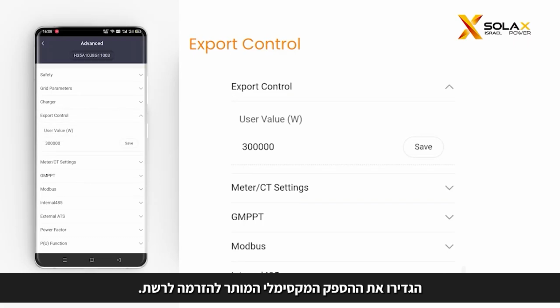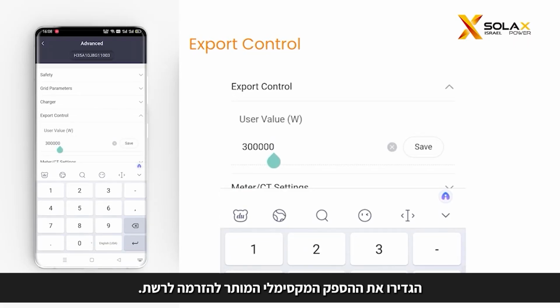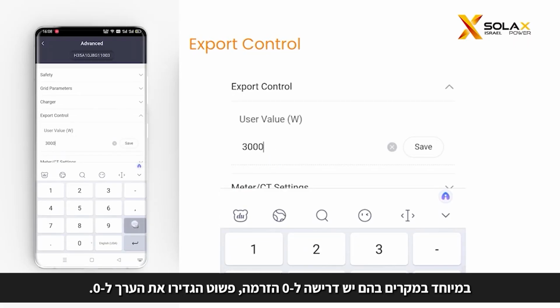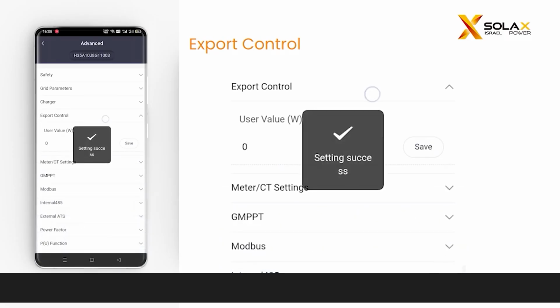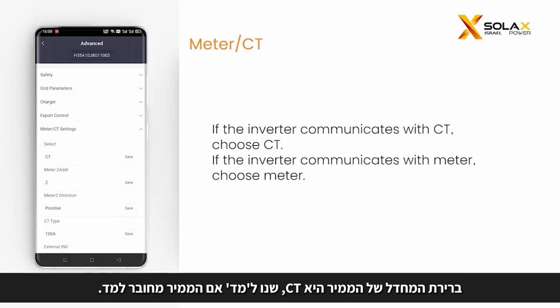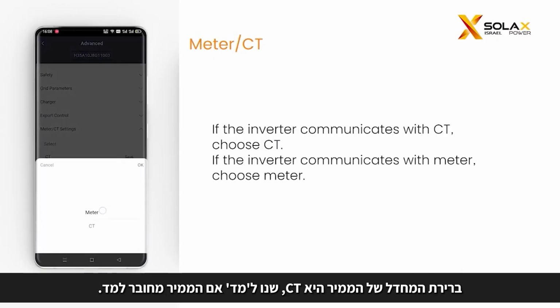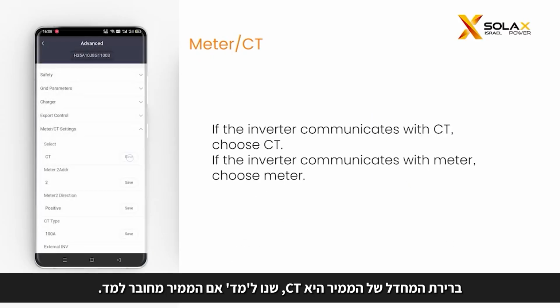Set the system maximum allowed feed-in power to the grid. Especially, when there is a zero injection requirement, just set the value to be 0. By default, the inverter is set to CT, change to meter if the inverter is connected to a meter.